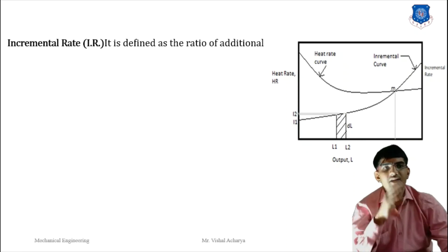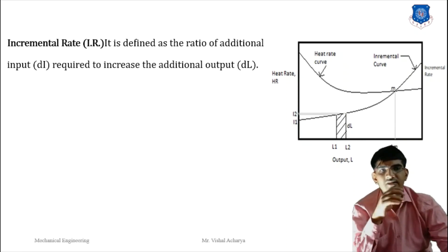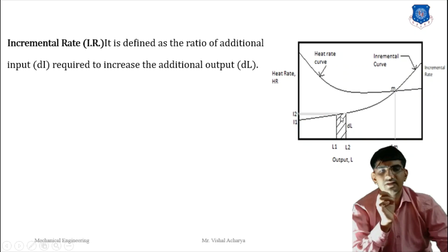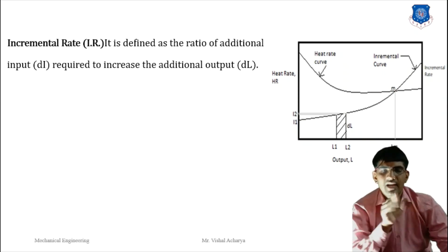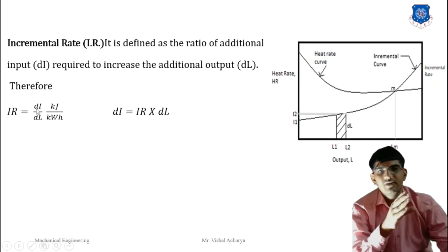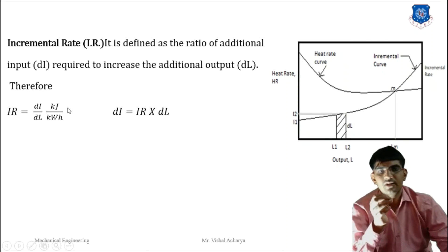Next is the incremental rate. It is defined as the ratio of the additional input required to the additional output obtained. As shown in the figure, additional input yields additional output. For small parameters the relationship is approximately linear, but as parameters increase the curve becomes non-linear. This non-linear curve is called the incremental rate curve. The incremental rate = additional input / additional output, with input in kilojoules and output in kilowatt-hours.